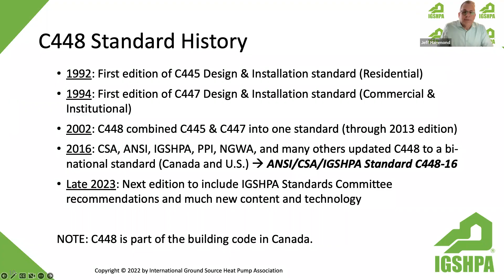Let's first off define a standard. This can be confusing when we talk about standards and codes and guidelines and everything else. But a standard is simply a set of technical definitions and requirements for design, installation, manufacturing, testing, and certification, primarily to protect customers. In this case, purchasers of ground source heat pump systems. So it gives us a minimum, what needs to be done in order to have a good installation. It's developed by an SDO, Standards Development Organization. I read off those acronyms earlier. And so that's recognized by each of the countries' development organizations. It's typically based on a set of minimum requirements. So it's not a design manual, as I mentioned. These are the minimum requirements in order for that installation to be successful.